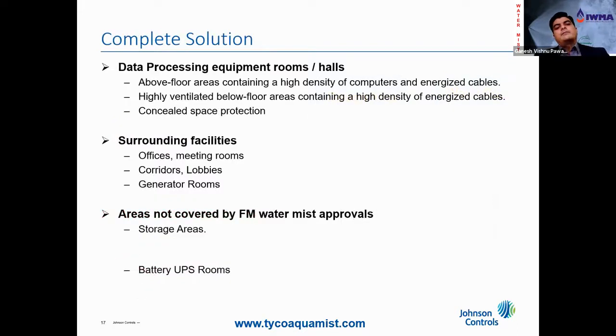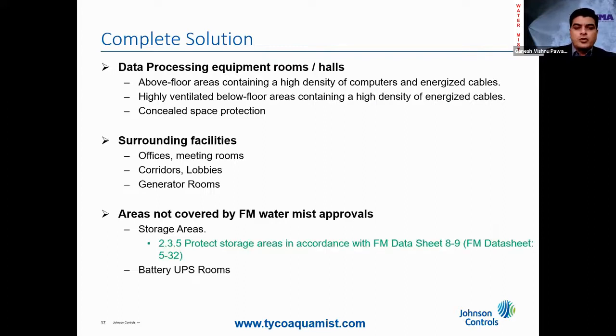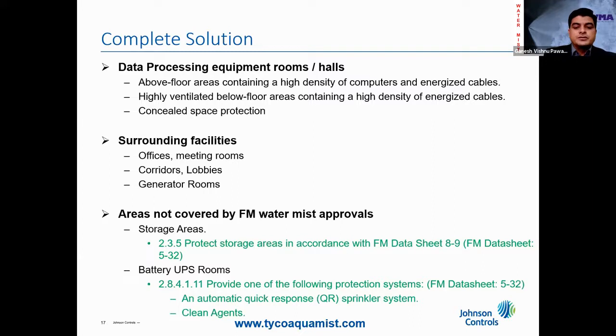Now, in order to provide a complete solution to the customer, we know that we protected the data halls and the surrounding areas with water mist. But what about the areas which are not covered by FM? As per FM datasheet 5-32, we can protect the storage areas as per FM datasheet 8-9. For the protection of battery rooms, we can consider a quick response sprinkler system, or we can choose clean agents. In line with the customer's requirement, we provided the storage areas and the battery UPS with sprinkler systems.